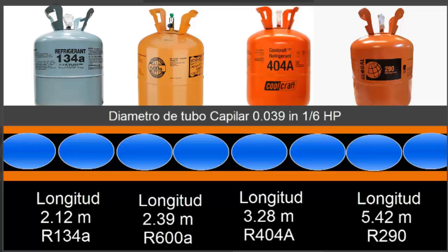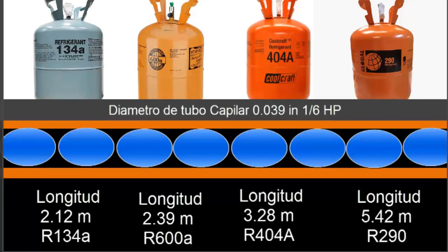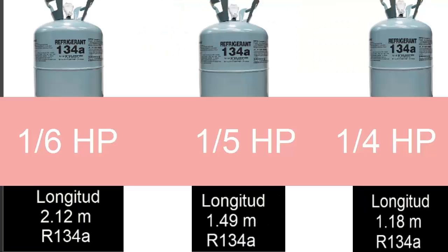It is important to mention that the ideal lengths for a capillary are those that are very close to 2 meters. Many times when the length goes well above that, the recommendation is to change the diameter of the capillary. Another important feature to observe is that the length of the capillary increases for each refrigerant as the HP of the compressor decreases.